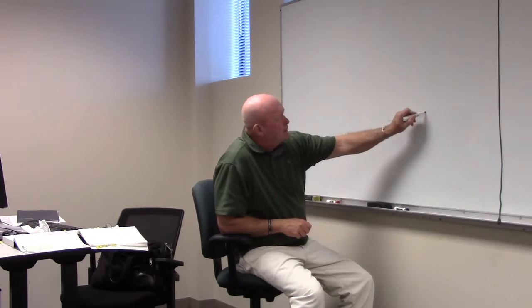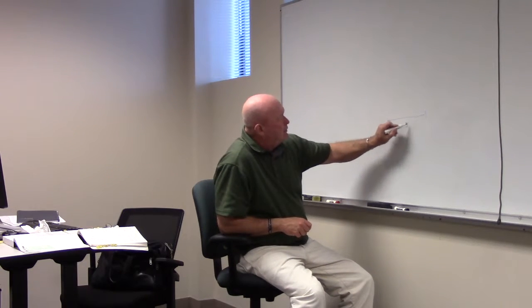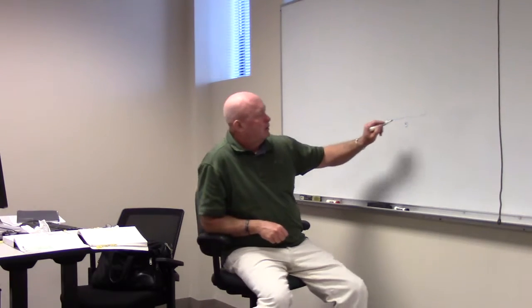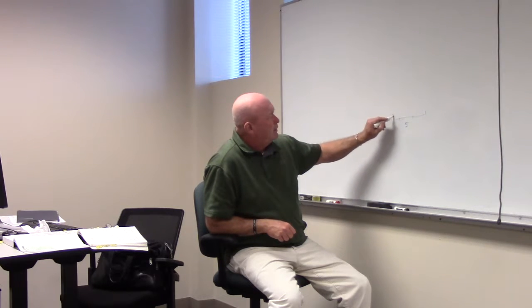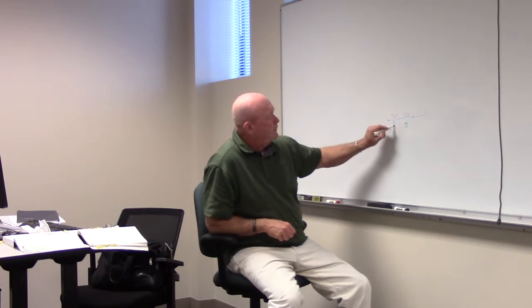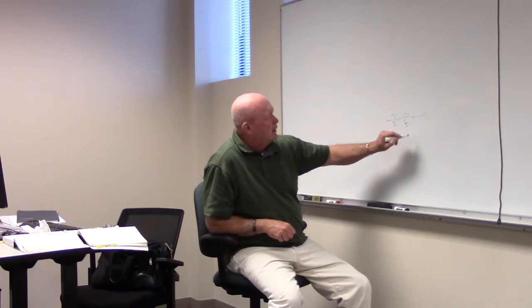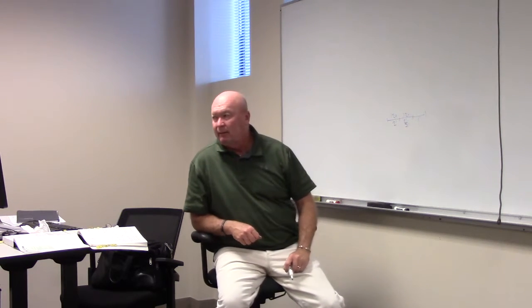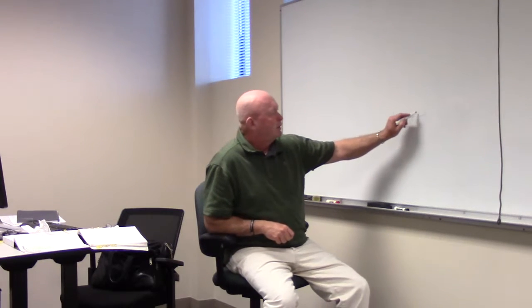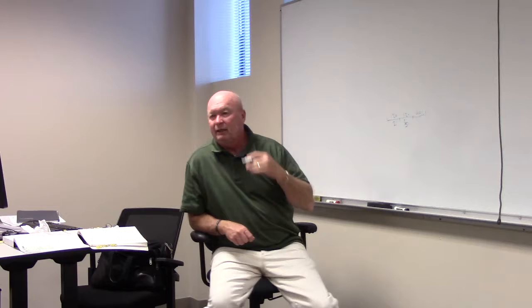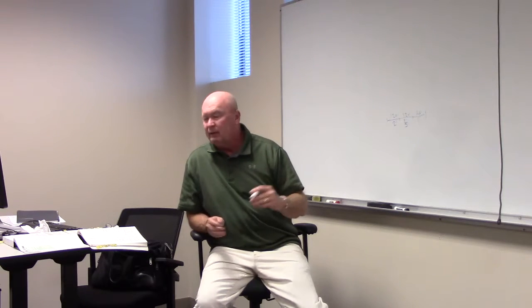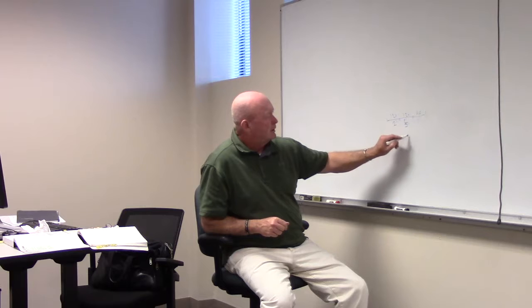So 120, is that what it said? So if we had a 5 foot piece of track, how many volt-amps would that be? So it's 120 what? Per 2 foot. Every 2 foot. So you have 120 here, 120 there, that's 2 foot, 2 foot, and this is 1 foot. How much is that 1 foot going to be? 60. Nope. How much is that 1 foot going to be? 120. Thank you, 120. It says for anything over, you have to count it as a whole. So that becomes 360.